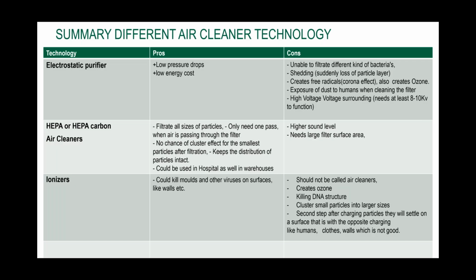There are others. Electrostatic air purifiers. These typically have low pressure drops and a low energy cost, and they attract dust and other types of contaminants by electrostatically attracting them to plates. So they have the potential to work in certain environments, but unfortunately they've also got some issues. Maybe they can't filter the different kinds of bacteria. They can shed, so you suddenly get a loss of a particle layer, which will go into the building. They can create other issues like free radicals and ozone, and there are typically high voltages needed.